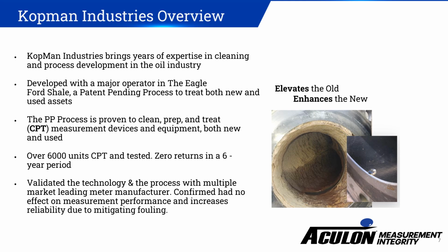New and/or used equipment can be brought to as good or better condition than a meter was when it was new. And over the course of this past 7 years, Kopman has treated over 6,000 units utilizing Aculon's technology. This long, dedicated research and development process and time in this project has demonstrated the effectiveness and reliability of the treatment in preventing fouling and ensuring optimal meter performance. Increasing reliability in the meter, decreasing the uncertainty of the meter was the focus of Kopman's overall objective over this project for the last 7 years.